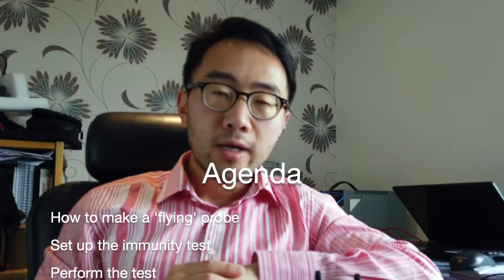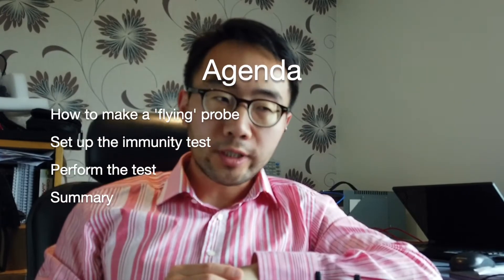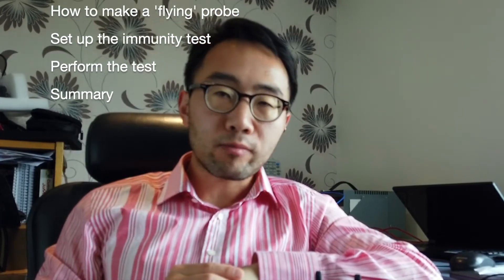Capacitive injection probe methods we use successfully reproduce the BCI failures in the same frequency range. Therefore, in this video, we will demonstrate how to make a flying probe, how to set the immunity test setup, and demonstrate by using the flying probe injection method that we can reproduce the same BCI failures.